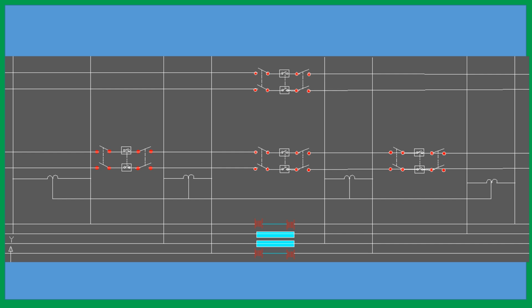The question is how to modify it. One thing we can do, we can jumper the neutral section. Neutral section is dead. So use a motorized double pole isolator. As both sides of the neutral section are under power off condition, a motorized isolator is safe. A double pole isolator is safe because current is not flowing. For feed action you can close it, but when you close it, the current will not immediately flow through the double pole isolator. So it is safe.